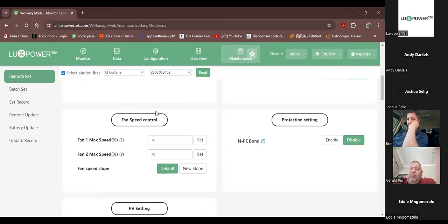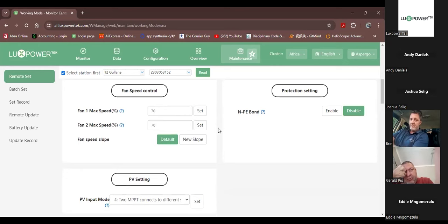Particularly, you must remember that the machine underneath has three fans. The left and the middle fan are dedicated to cooling the DC to DC and AC to DC side, and the right fan cools the MPPT. I know some clients have their machines installed inside for various reasons, and it can become a bit of an irritation. But unfortunately, we can't eliminate the fans. So always remember when you're selling an SNA to advise your client that these are fan cooled. When it's charging or discharging the battery, the fans will come on periodically. And when it's harvesting solar, the fan will run probably for most of the time that it's harvesting the solar, especially when the power being yielded goes very high.